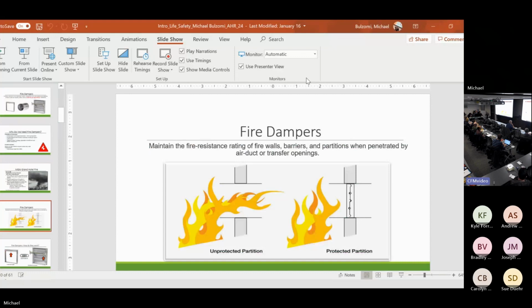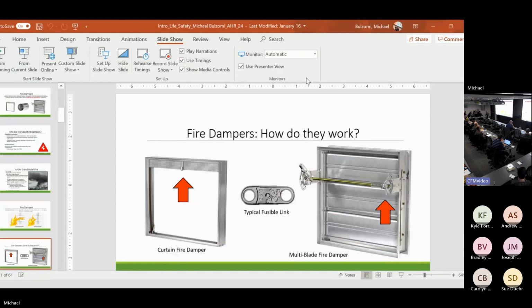Again, if this is a rated wall, it's going to protect the fire from going through, but if it has a giant hole in it, the fire is going to find that hole, and that's where it's going to want to go. So you have to protect that partition to prevent the fire from transferring from one side of the wall to the other. And fire dampers, man, the technology has not changed in over 100 years.